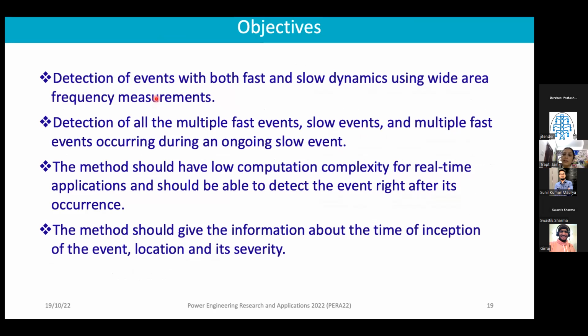We have utilized only frequency measurements to identify whether an event happening has fast dynamics or slow dynamics. It's also possible that more than one event is happening at a time, like multiple fast events, because multiple lines can trip. Fast events mean a transmission line fault or a line trip. Slow dynamics could be events like generation loss or load loss.